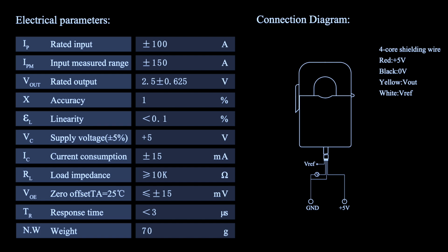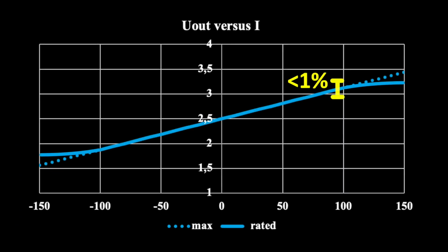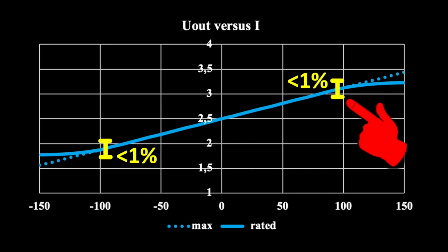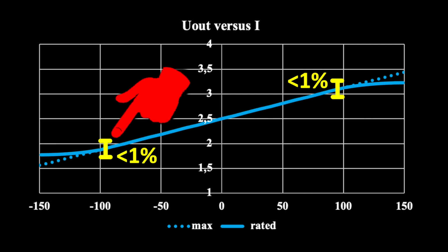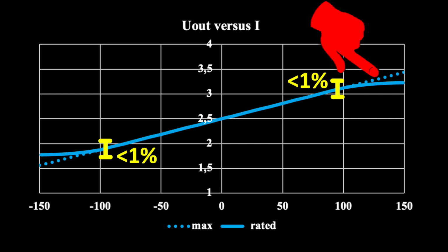According to the datasheet, the rated accuracy of our sensor is 1%, meaning the maximum deviation between measured and actual current can be up to 1 ampere. It's corresponding to an output voltage deviation of 6.5 millivolts. This measurement error can be eliminated by calibration. In other words, you are correcting with the known result of a test measurement. We can use the sensor in the extended range up to 150 amps, but its accuracy is getting worse then.